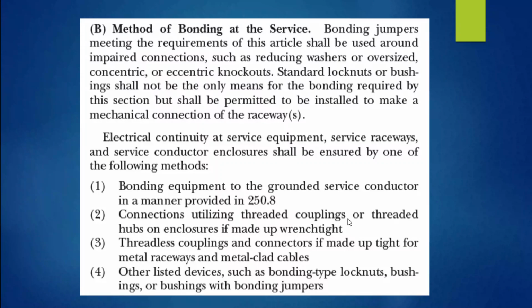Connections utilizing threaded couplings or threaded hubs, and we see that in all of my graphics where it comes into the top. You see the threaded hub. But let's go back and I'll illustrate. On that overhead, what if I have 20 feet I have to go? So we have the hub on top of the meter enclosure, but now I need to go 20 feet up to the weatherhead. Well, every joint of rigid, let's say, is only 10 feet long, so I need 2 sticks. They're threaded, and I'll have a coupling. That threaded coupling is bonding those 2 raceways together. It is acceptable to utilize that in order to get you that additional length of raceway you need. So that's the example, and it comes into that threaded hub. That's what we see in most of the graphics that I'm showing at this point.